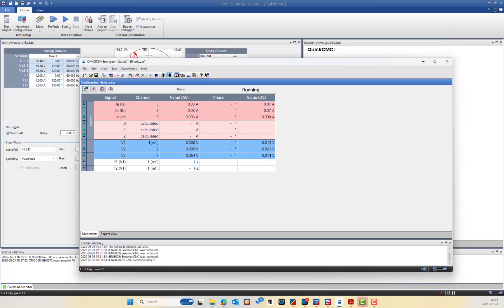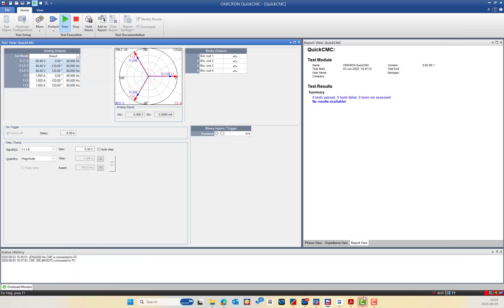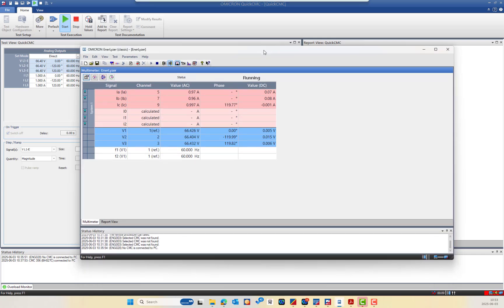I will inject using the Quick CMC module at nominal value. As you can see in the Analyzer Classic, V1 is 66.4V at 0°, V2 is 66.406V at -120°, V3 is 66.4V at 120°. However, for the current, only IC is showing a phase angle of 119.9°.